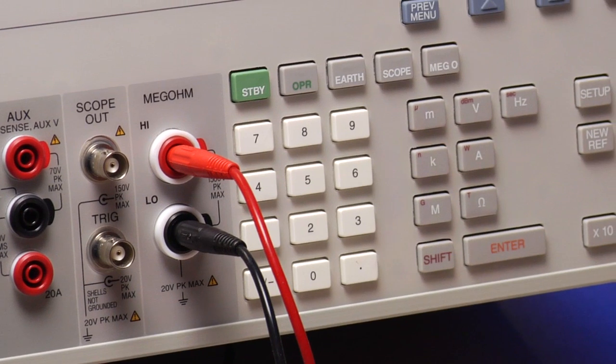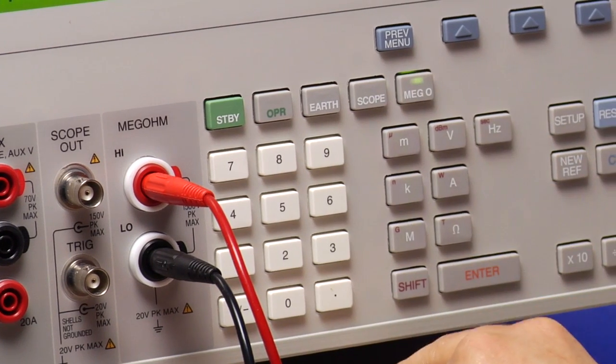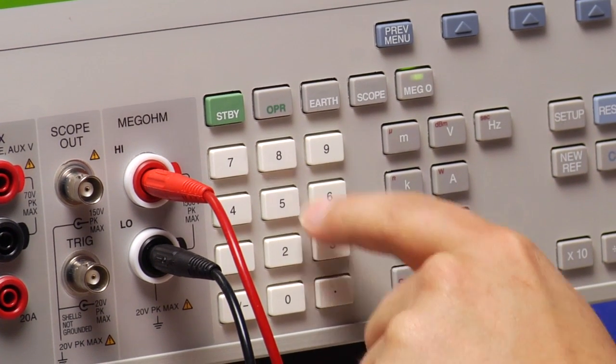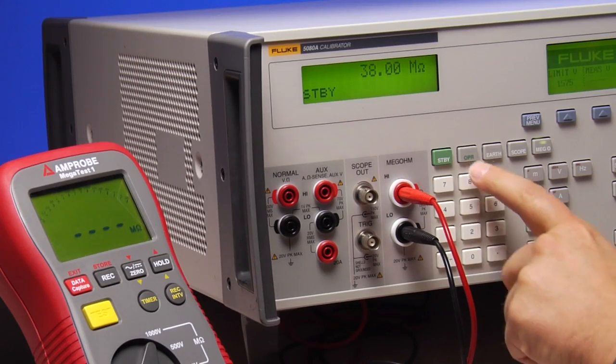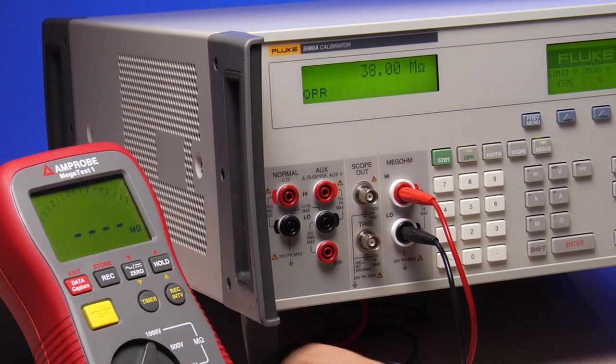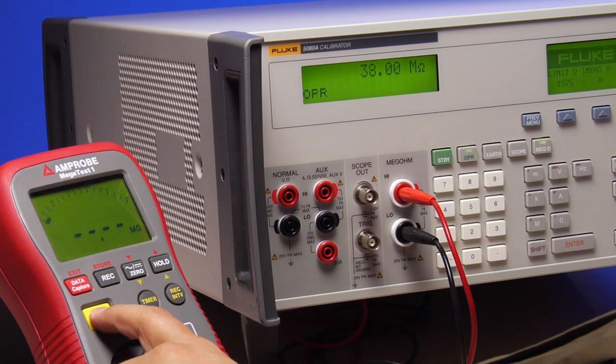The mega ohm meter calibration option enables safe and efficient calibration of insulation testers. This option sources insulation and continuity resistance and measures voltage and current inputs.